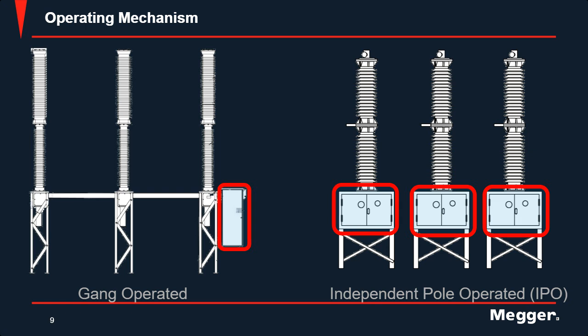So now that we've talked about the difference between live tank and dead tank, let's talk about the operating mechanisms. You have two different types of operating mechanisms: gang operated and independent pole operated, or IPO. Gang operated means that the switch can be operated simultaneously by a single mechanism. Gang operated ensures that all poles of the switch open or close together, which is important for safety and coordination of the electrical system.